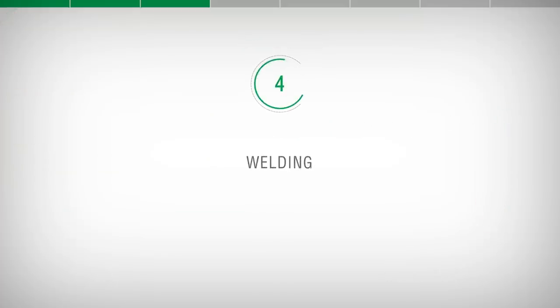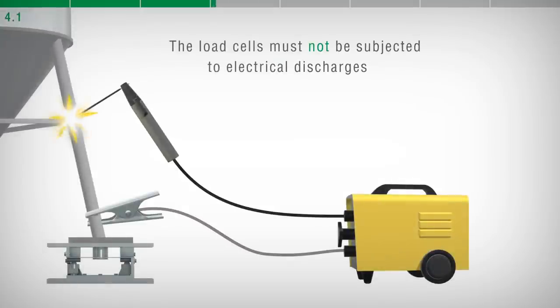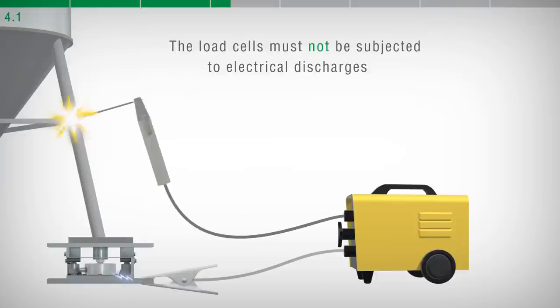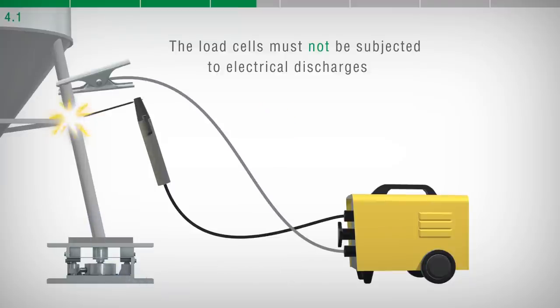Welding. It is recommended to avoid welding while the load cells are installed. If this cannot be avoided, place the welder ground clamp close to the required welding point to prevent sending current through the load cell body.